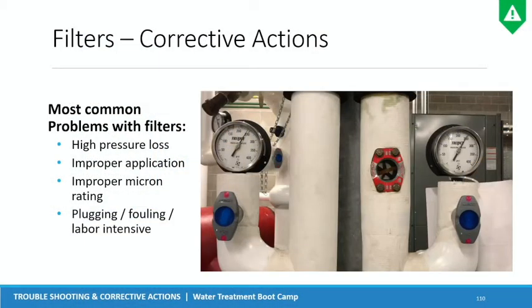Or I can't tell you how many times I've seen a new construction, a pipe fitter's putting in a filter housing. They're putting it in where they were told to put it in. Maybe they don't question it. And you take your supply and your return off the same pipe, so you have no pressure differential to actually push through that filter housing. So then you go and you test a loop that you thought had chemical treatment in it, and you get an erroneously high number, coming to find out that it's not plumbed right, so the chemical that was added was never actually added into the system. And I know there's at least one person in the audience that we've gone through that with.